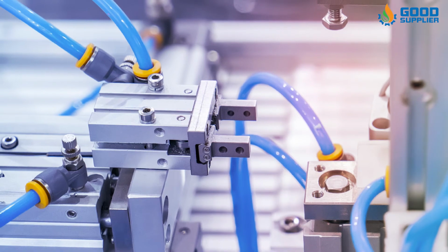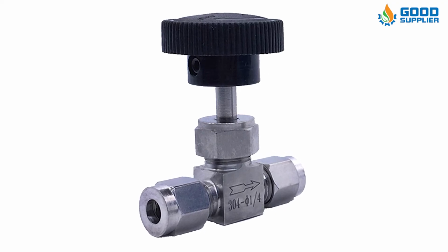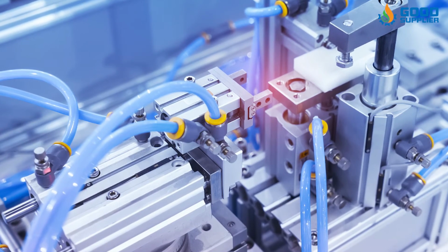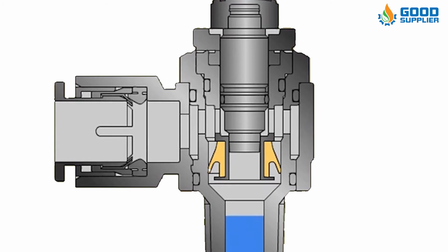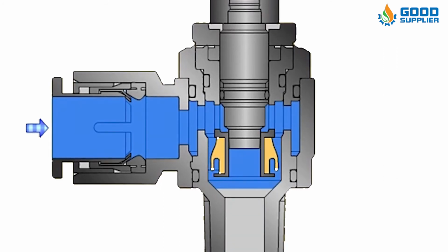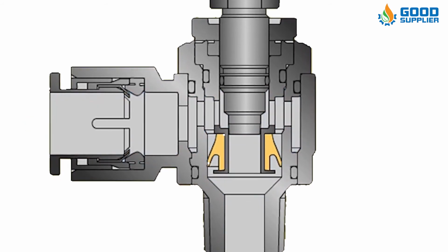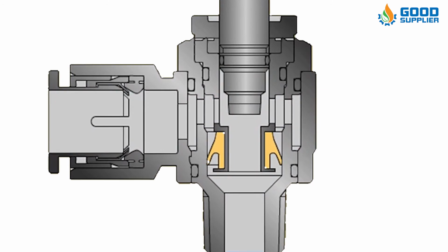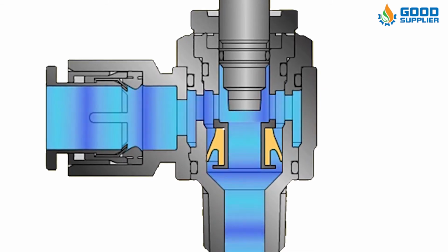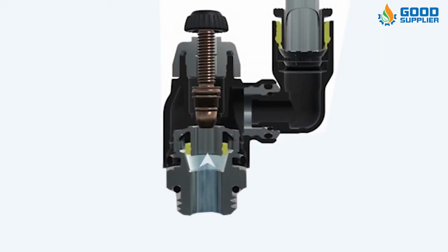What are the different types of needle valves? A manually operated threaded needle valve is the most common type of needle valve. However, two additional variants are motorized and angle. Motorized needle valve: these needle valves don't have a handle for manual operation, but instead use an electric or pneumatic actuator to connect to and turn the plunger. These can be remotely controlled, used in a closed-loop system, and put on a timer to control the flow rate remotely and accurately.